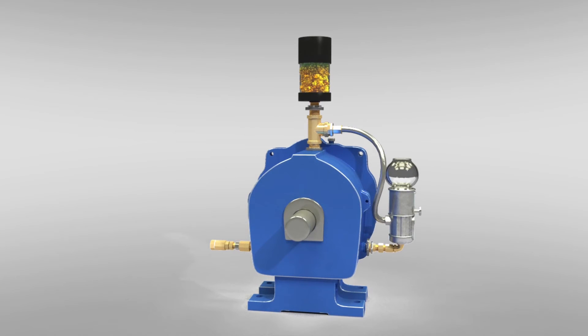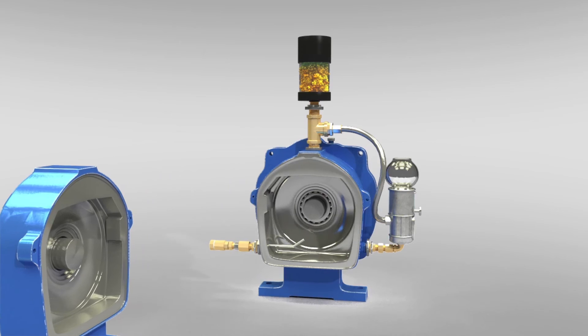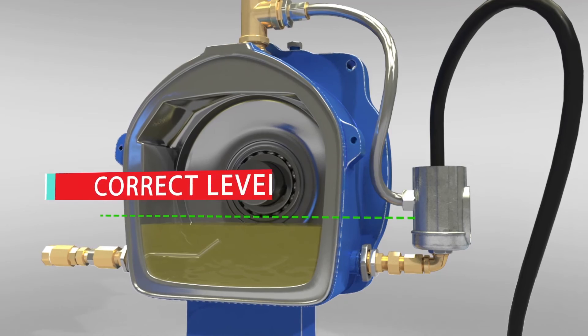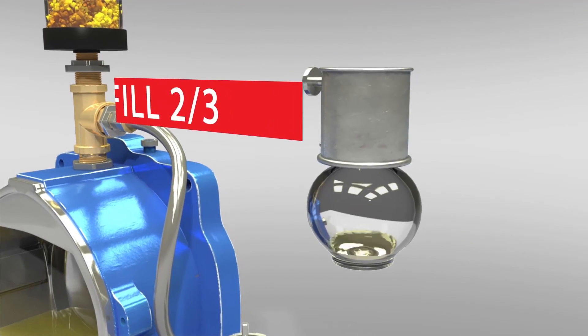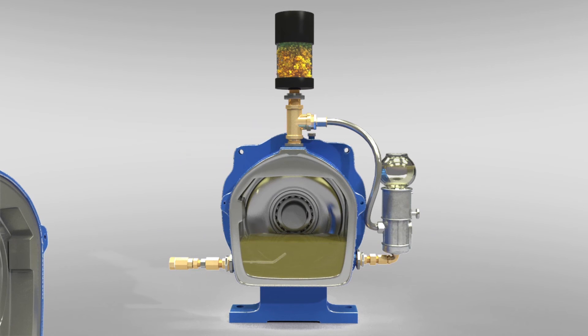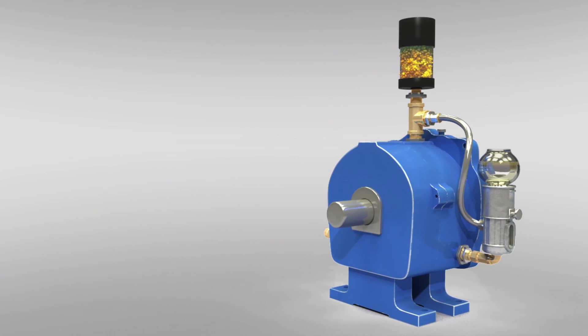Keep the equipment full. Filling the equipment once you've installed an oiler is simple and easy. Simply remove the bulb of the oiler and fill the lower casting until the correct level is achieved. Fill the oiler bulb two-thirds full and then replace. This will assure you've always got the correct level of lubricant, thus optimizing your lubrication.